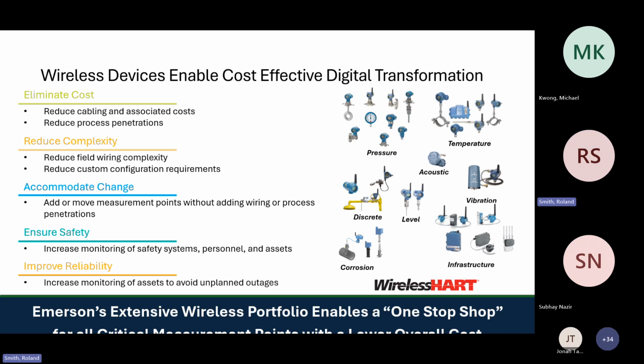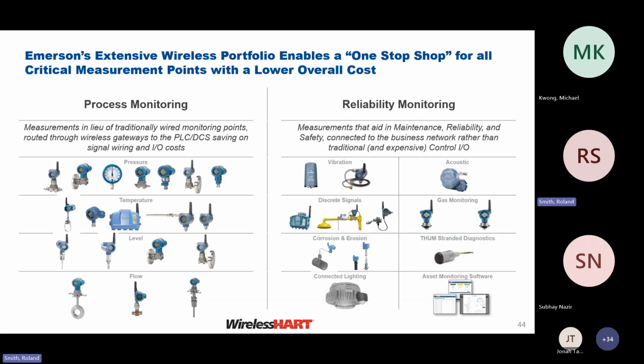We can add a device where cost inhibited it before. Safety is another reason why customers are implementing our products, and overall reliability, because we can give them those measurements they never had before to make safe decisions and make their plant run more reliable than ever. So you can see here we run into basically process monitoring, pressure, temperature, level, and flow for the most part. And then we get into the reliability world where we're looking at vibration and PRV liftoff and so forth.